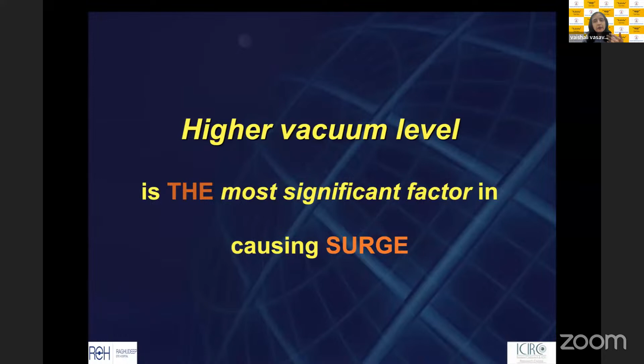So now how can we minimize this surge? The most important thing is that there are good machines. The tubing compliance: the irrigation aspiration tubes in the good old days used to be very, very pliable. Now we have much stiffer tubes, smaller bore tubes. The ideal would be steel tubing. If you want to really eliminate surge from the system, the ideal method would be to use a steel or rigid metal tubing, but that's not a practical thing. We now have rubber and PVC materials which are very stiff and their wall is thick, so their collapsibility is less. So that is what the industry or the machines can do.